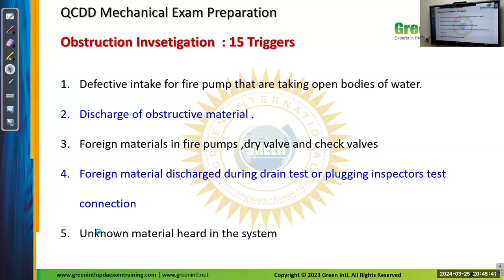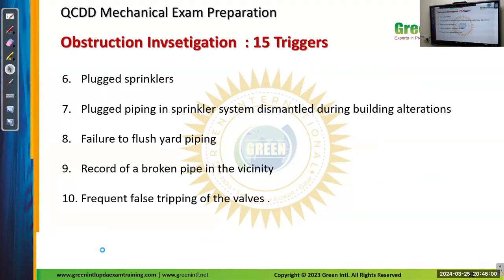So defective intake of fire pumps taking suction from open bodies of water, discharge of obstructing materials, foreign materials in fire pumps, dry valves and check valves, foreign materials discharged during drain, unknown material heard in the systems. I think any sound or something related to that. Plugged sprinklers. So what are plugged sprinklers?